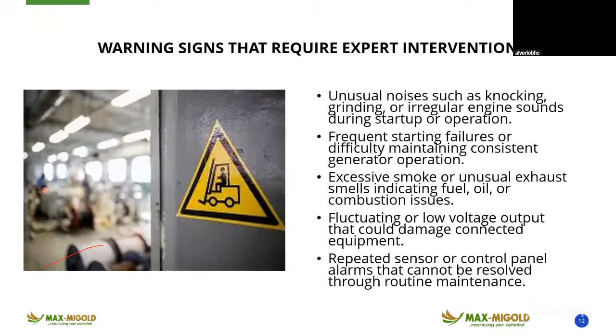Frequent start failure or difficulty maintaining consistent generator operation. If you experience hard starting, or the generator is working and suddenly shuts down, you know that something is wrong. Excess smoke or unusual exhaust smell indicates a fuel, oil or combustion issue. When you notice all this, escalate to the right service provider. Fluctuating or low voltage output is another fault associated with generators. If you are experiencing this, escalate to the right channel. Also repeated sensor or control panel alarms that cannot be resolved through routine maintenance. Anything of this you observe, reach out to the appropriate vendor to respond and correct.